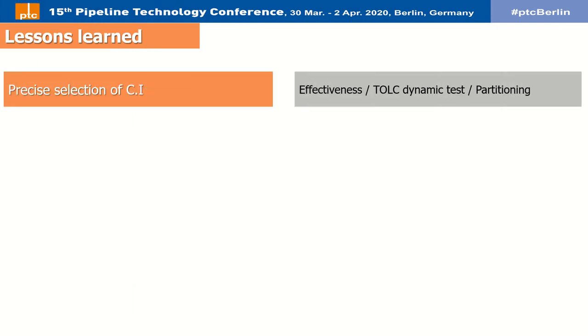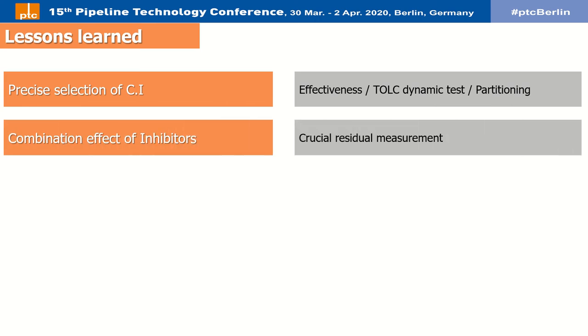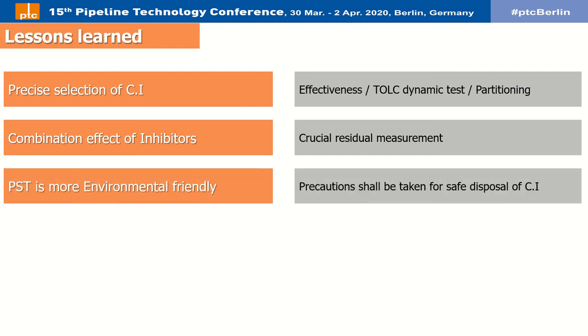Moreover, each batch of corrosion inhibitor must be precisely tested for effectiveness and partitioning. Most importantly, corrosion inhibitors and hydrate inhibitors may have adverse effects on each other, producing undesirable polymeric byproducts such as heavy compounds of paraffin or olefin, which leads to a drastic reduction in heat exchanger efficiency downstream. Consequently, stringent precautions are required to perform compatibility tests and to avoid injection beyond the recommended dosage to prevent sticky substances downstream.